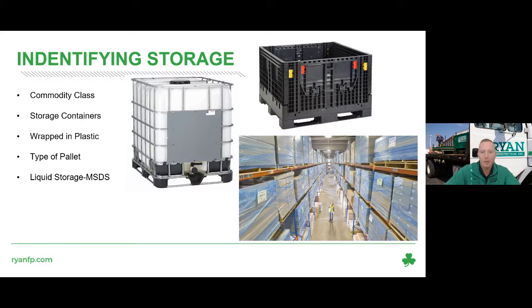The first thing we look at is what you're storing, to determine where it falls in the spectrum of commodity classifications. I pulled this directly from the National Fire Protection Association, NFPA 13. It identifies that, for example, a textile is a class 3 commodity, and so on down the list, which really helps take the guesswork out.